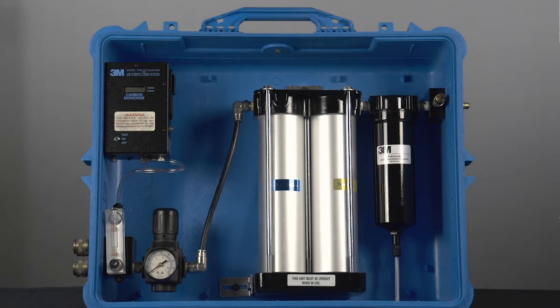The maximum number of users per panel isn't just the number of panel outlets. Rather, it also depends on the inlet air pressure and volume, the pressure drop across the panel, and the pressure required for the respirators. The maximum number of users may be estimated using the following methods.